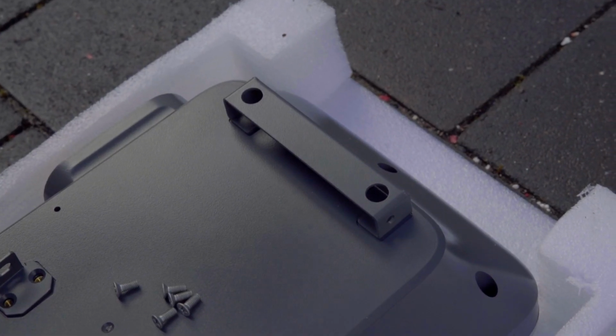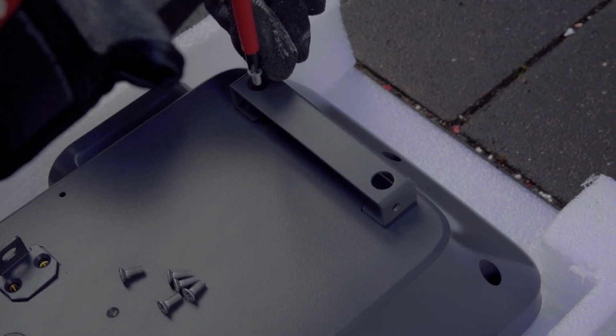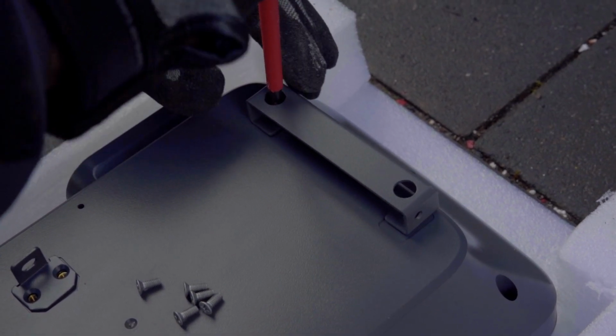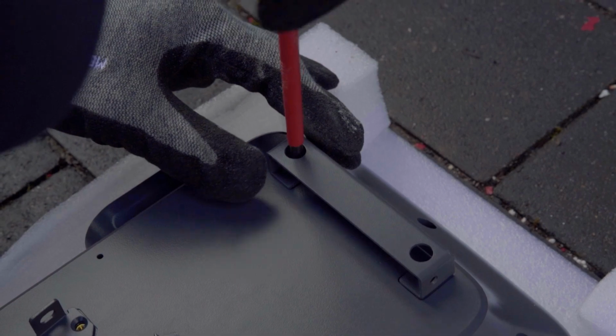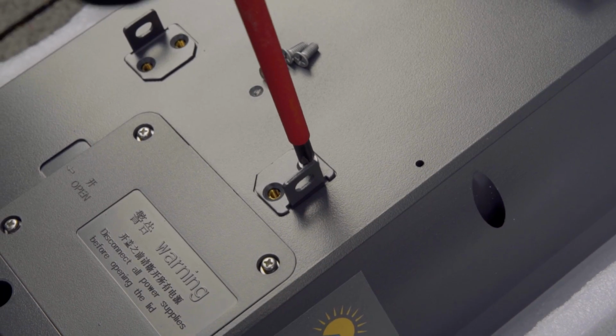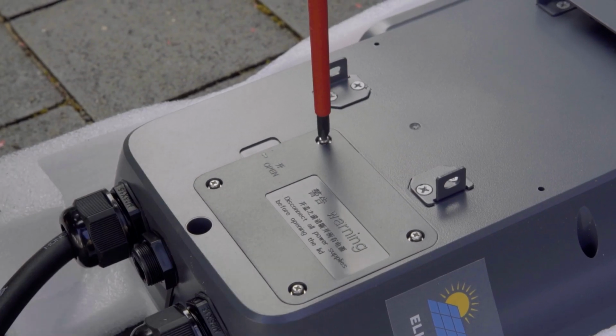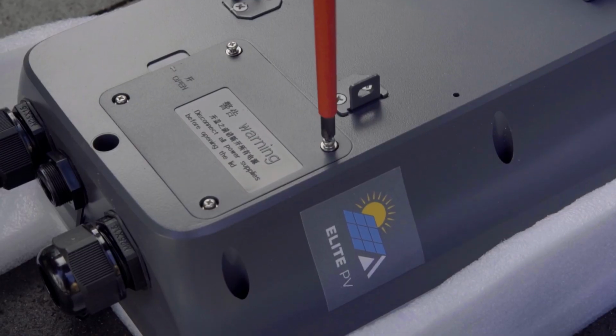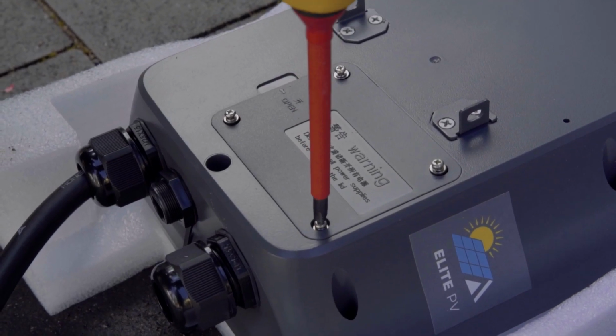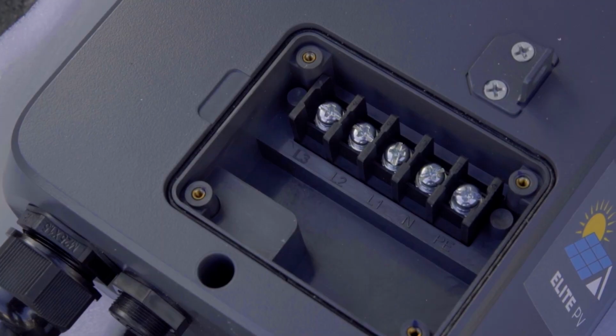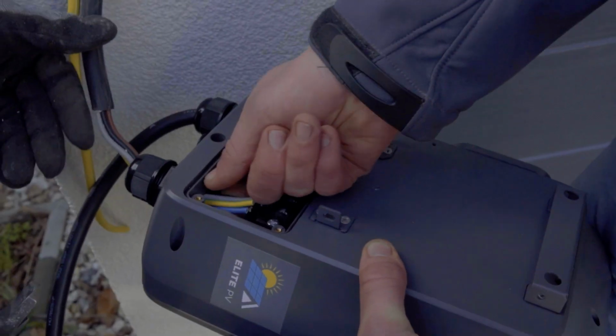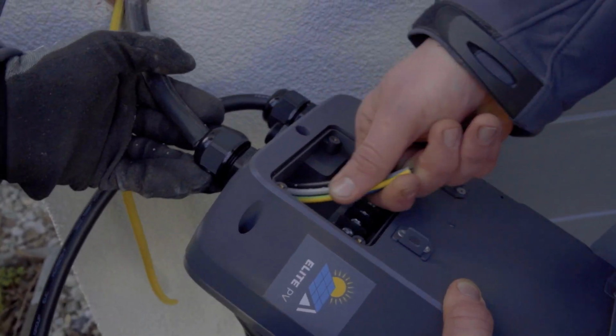First, place the charger up on a soft ground to protect the surface. Fix the upper and lower mounting brackets on the back side of the charger by screwing with M4 screws. Then, remove the back cover plate and with a screwdriver loosen the M3 screws. Insert the AC cable into the charger through the AC cable gland located at the bottom.